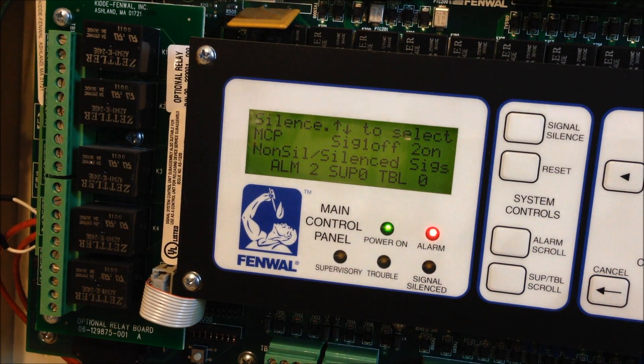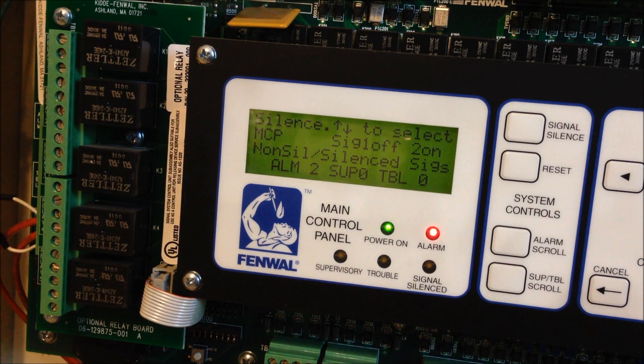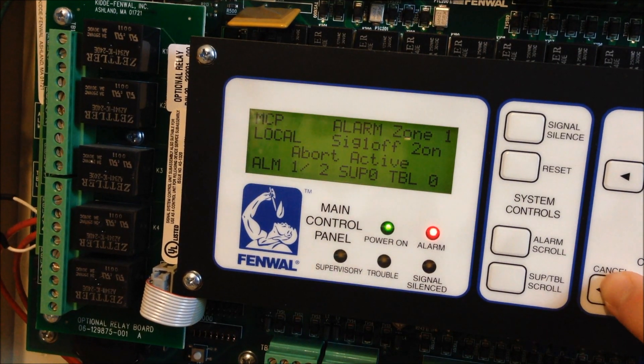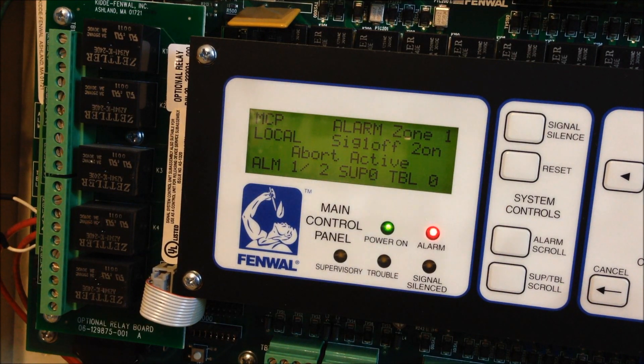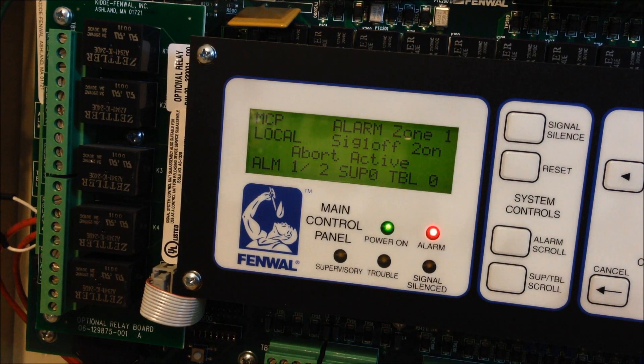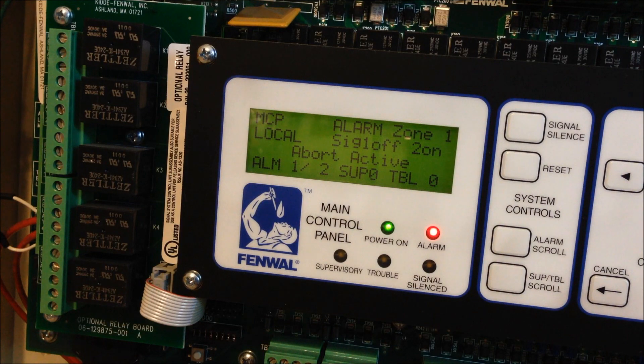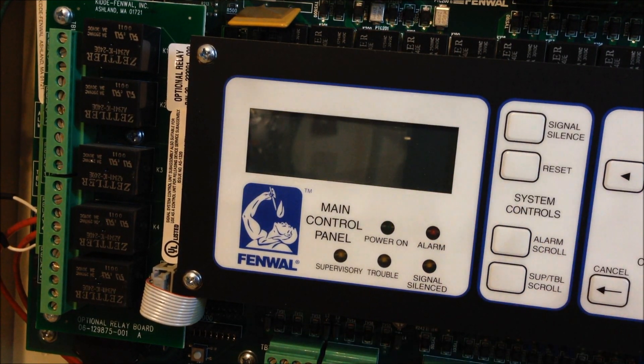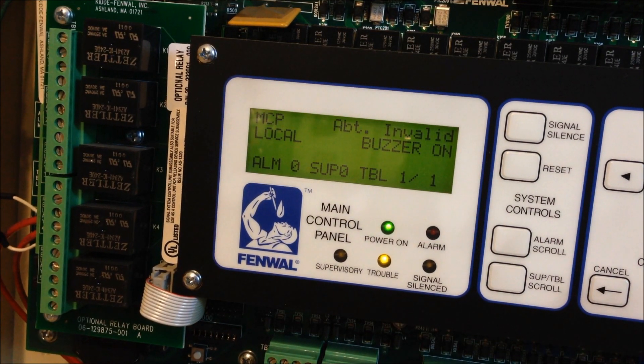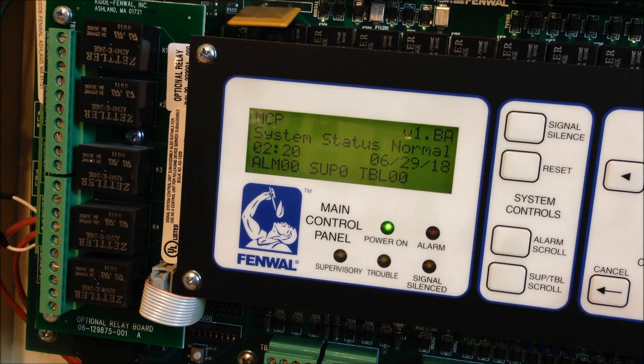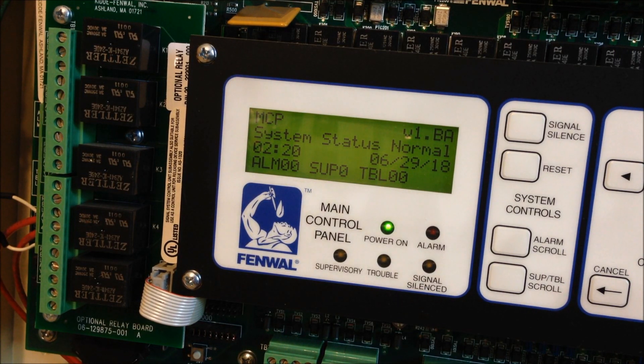I've silenced the horns, but the strobe and panel buzzer continue to sound because they're non-silenceable, and I'm still holding the abort button down — so the system will not discharge. If there were an accidental activation or somebody has manually put out the fire, the person at the abort station can continue holding it down and the panel can be reset. Once reset, I release the button and we're back to normal.